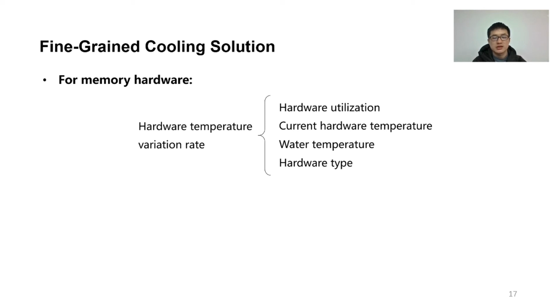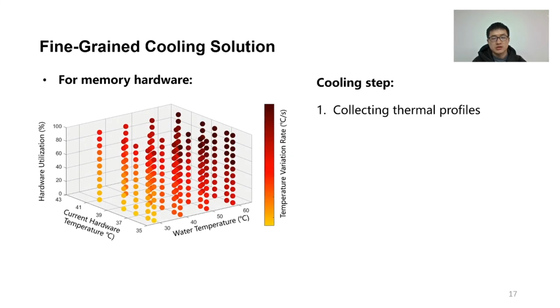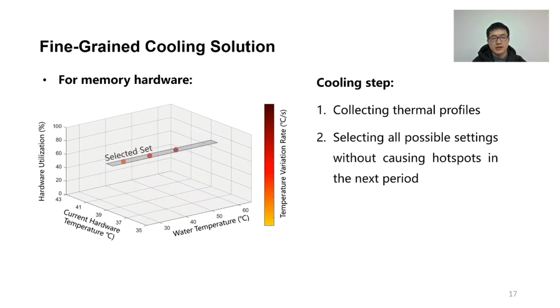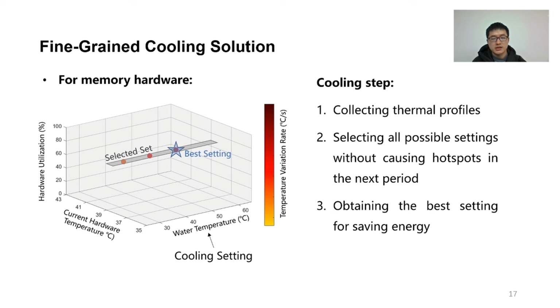Based on this observation, the cooling solution first collects all thermal profiles in advance. Then, it selects all possible settings that keep the hardware temperature in the next period below its safe operating temperature at runtime. Finally, it obtains the best setting from the set to minimize cooling energy by maximizing the water temperature directly.